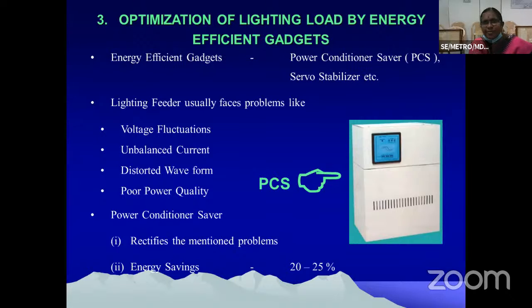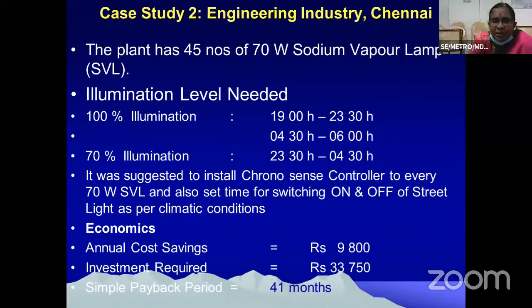Optimization of lighting load by energy efficient gadgets, say power conditioner savers, servo stabilizers. The lighting feeder usually faces problems like voltage fluctuations, unbalanced current, distorted waveform, poor power quality. Power conditioner saver rectifies all the above problems and there is a potential for energy savings around 20 to 25%. Mainly in lighting circuits in industries, if they have a proposal to change the conventional FTL or sodium vapor lamp to LED, or the fluorescent tube light to LED, they have a lot of energy savings.